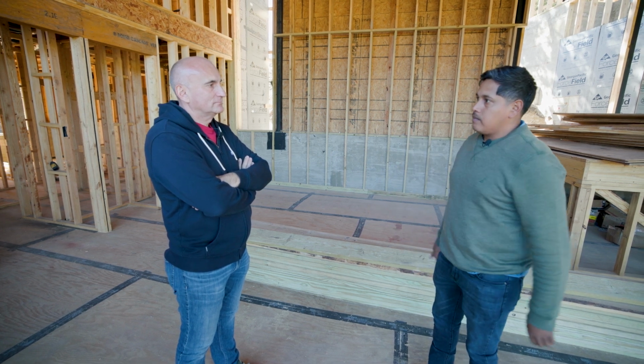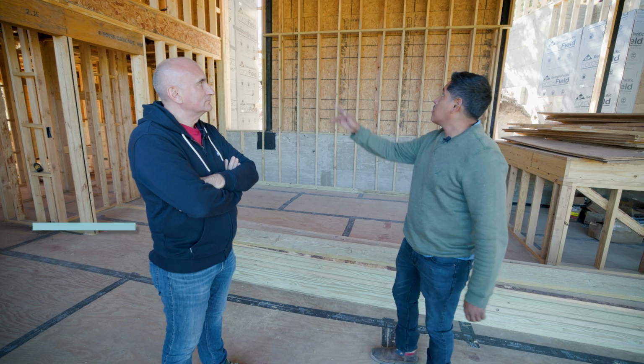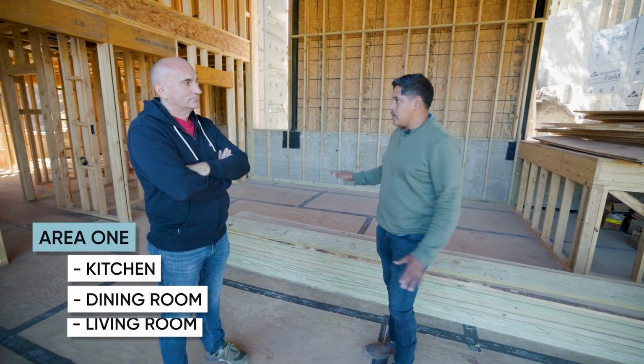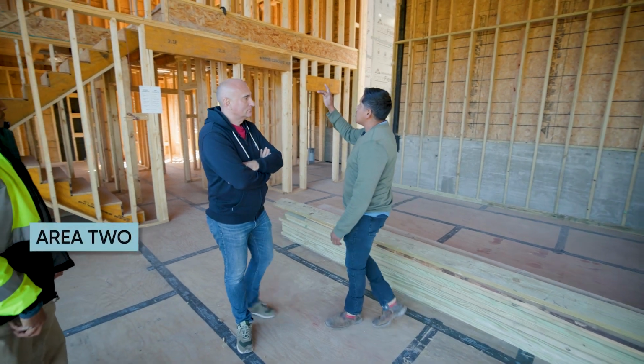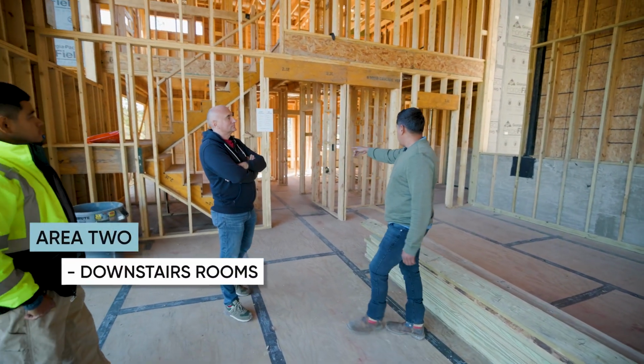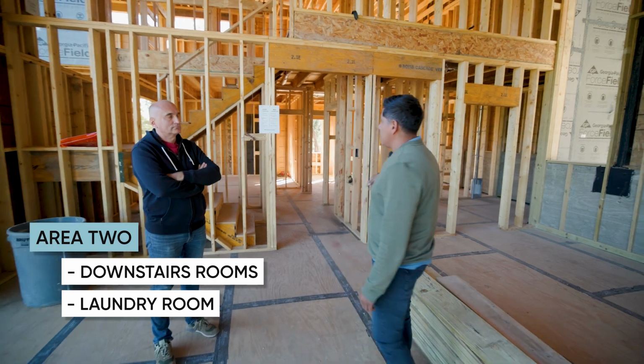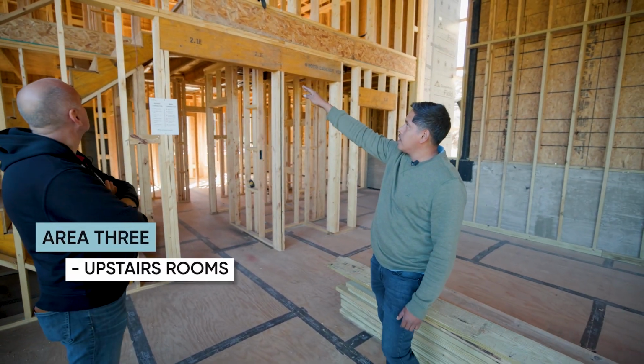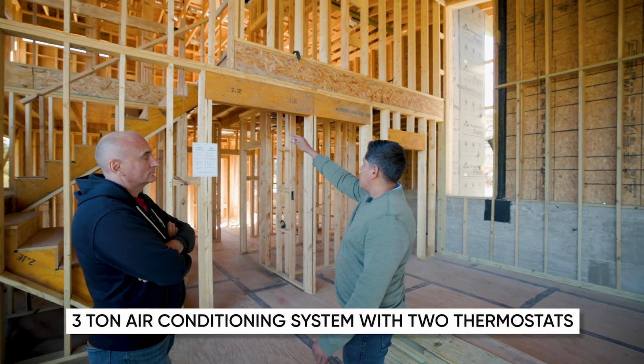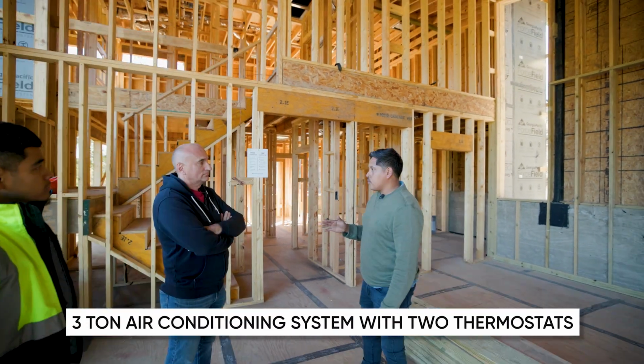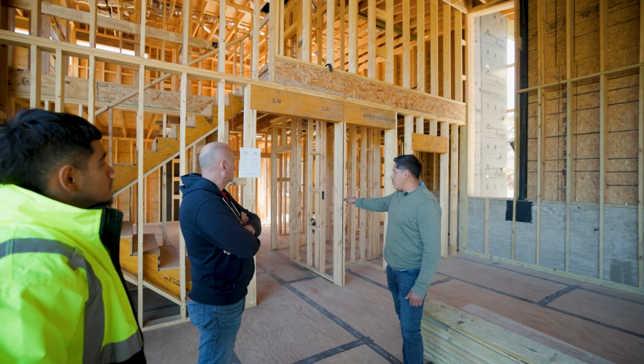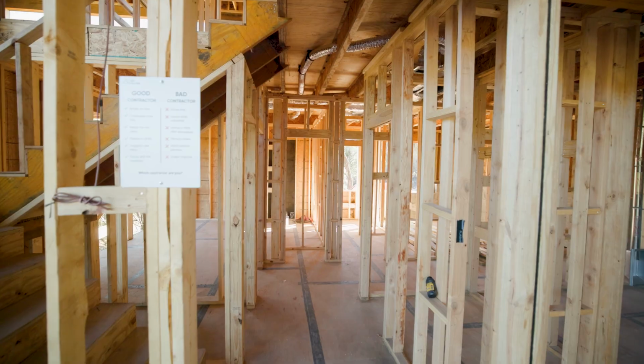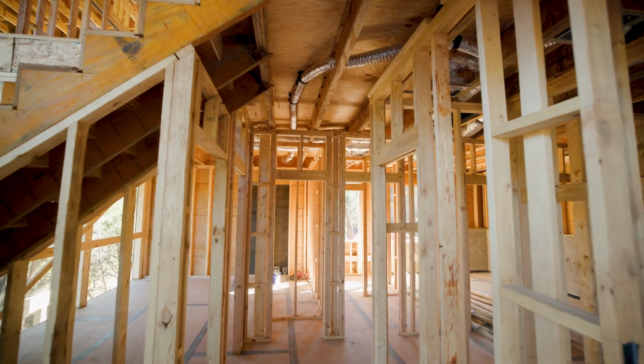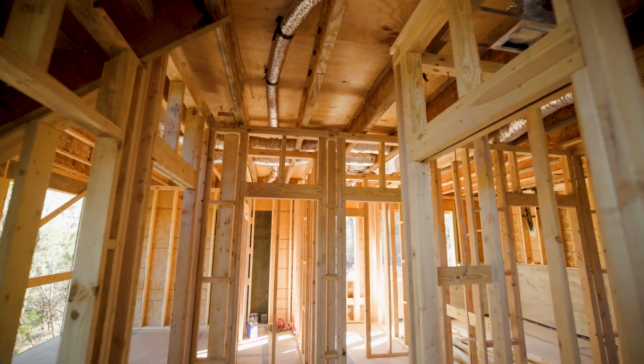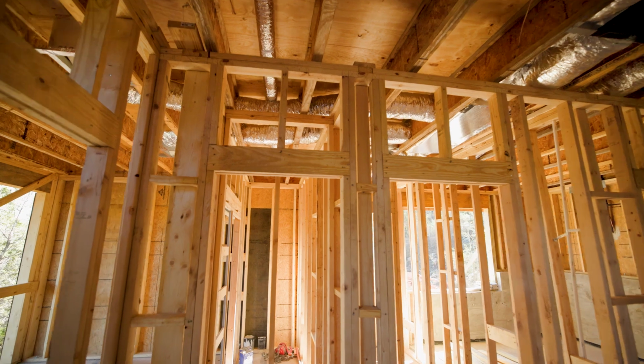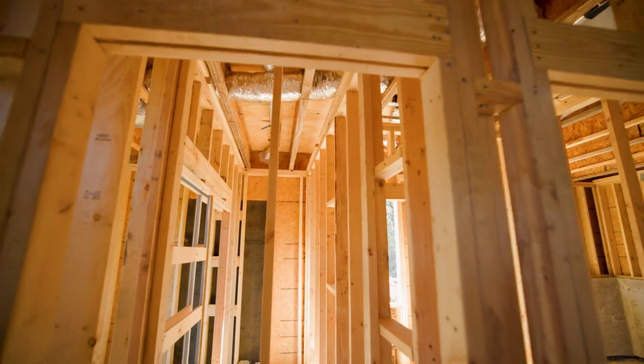have foam insulation. In this case, here we have a 3-ton system specifically for the kitchen, dining room, and living room. We have another 3-ton system respectively for the rooms downstairs to the laundry room. And we have another area which are the rooms upstairs. We're going to control those with a 3-ton system with 2 thermostats, since you want to have the temperature downstairs. If you like it at 75, let's say, and the person upstairs likes it at 78, everyone can have their temperatures set to their liking. Even one system can be off while the other is on.